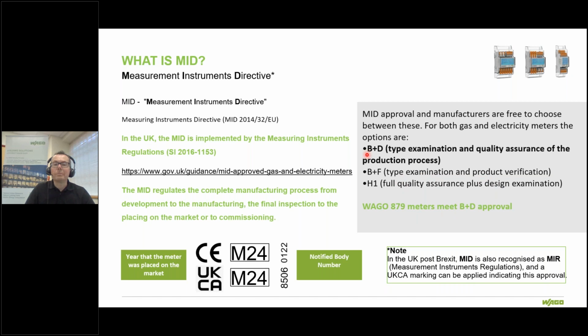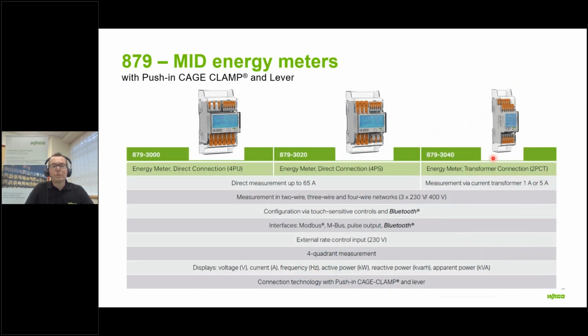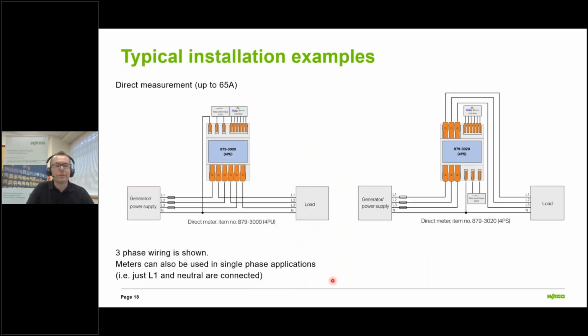WAGO 879 meters are under the BD category for quality assurance during the manufacturing process. So we're using our own 879 meters as an example of typical MID approved meters that are typically employed as sub-metering or individual meters for perhaps landlord-tenant arrangements. And so you can see that in our range here, we have direct metering. These are rated at up to 65 amps. And you'll see in a moment that the only reason there's two different types here is simply from a wiring configuration perspective. Notice the main power connections are all at the base here, whereas here they're in line. And a third type of meter is for current transformers, and I'll come on to that. And here we see the specifications that we'll touch on in a little bit more detail as we go through.